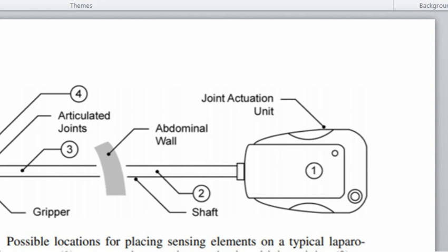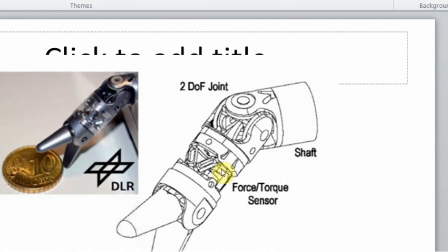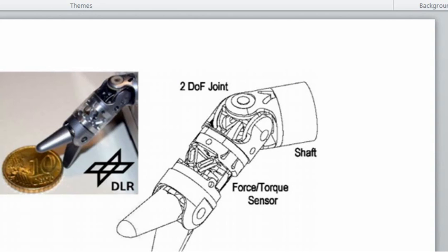At the German Aerospace Center, DLR, a researcher named Sobel has developed a digital force torque sensor for laparoscopic instruments. So in the picture, the sensor makes use of a hexapod structure known as a Stewart platform to locate 6 strain gauges for measuring force and torque using all of the 6 measurement axes. By taking advantage of such a special hexapod structure fabricated from an aluminum copper magnesium alloy, the sensor achieves good measurement sensitivity with a very satisfactory structure stiffness characteristic.